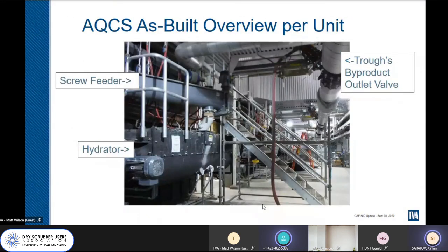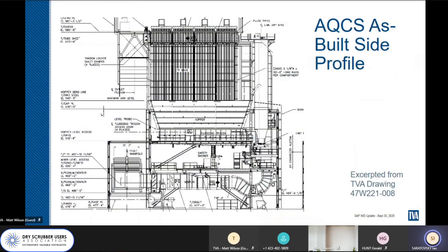Matthew, I think now's the appropriate time to ask this question that we got. What about maintaining velocities at low loads to keep that fluidized? Do you have any issues with that? So we have 4 of these in parallel, and at least on units 3 and 4, full load takes 4 of the modules to be in service. To keep it simple, if you come down to mid load, you take 1 module out of service. Now you have 3 in parallel in service. You come down to low load, you take another 1 out. Now you're down to 2 in service in parallel operation.